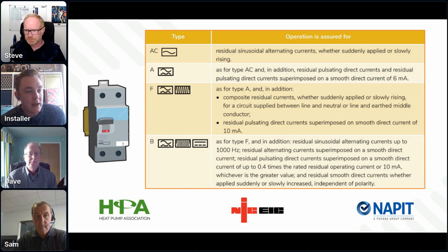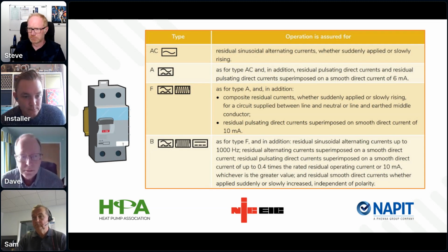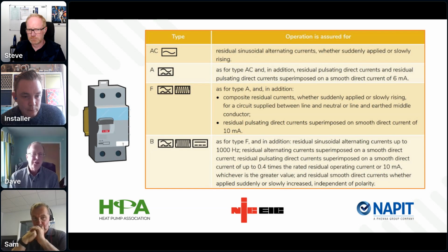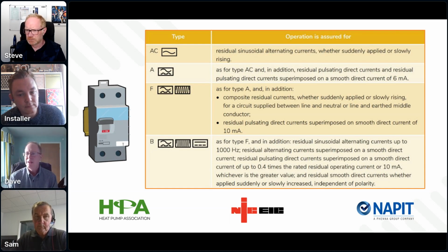No, perfect. And then Dave, coming to you, what do you choose if there's nothing to support your choice? Okay, so I'm just going to carry on with the question that Chris has asked in the chat, and one of the things we get asked is about Type B plus. Now, Type B plus has come onto the market from Germany and is produced to a German standard, which hasn't been tested or approved against any European normalized standards. So it's being talked about a lot as a possible RCD for heat pumps, but that one isn't recognised within BS 7671.